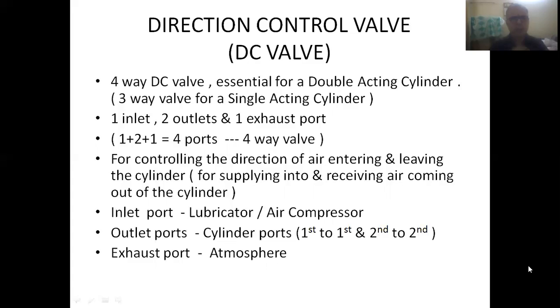Therefore it is called as a four-way DC valve. It will be controlling the direction of air that is entering and leaving the cylinder. Therefore it will be supplying air from one side of the cylinder, and at the same time it will be receiving air that is coming out from the other side of the cylinder. Therefore friends, it is called as a direction control valve.